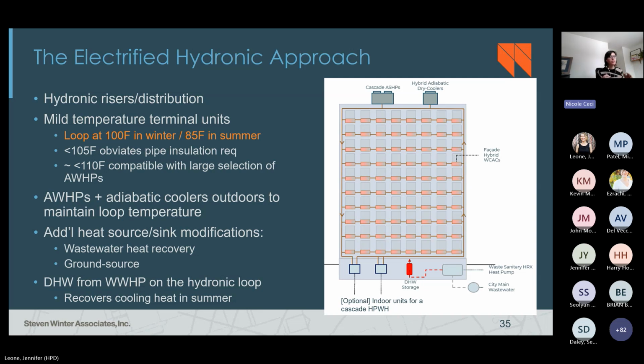And there are a couple of important points to call out about those temperatures. So one is that when we get below 105, we obviate some of those energy code requirements, the code requirements for piping insulation. When we get below roughly 110, it's a squishy number, we become compatible with a really wide range of air-to-water heat pumps that can feed that loop. And also, by not using chilled water for cooling, we're eliminating the potential for condensation to get on pipes, preventing corrosion and premature failure of that distribution piping.